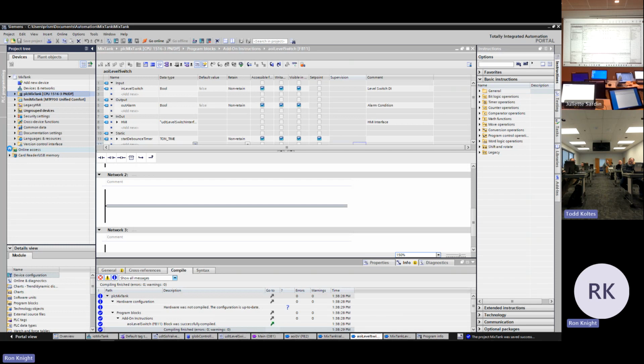And does that open a bunch of doors, doing that to Allen Bradley? You can only downgrade an Allen Bradley so far, and then you have hardware issues to worry about. So with firmware in Siemens, you won't be able to download firmware for a part number if it's not compatible. You actually download firmware from the Siemens website based on the part number of your PLC.